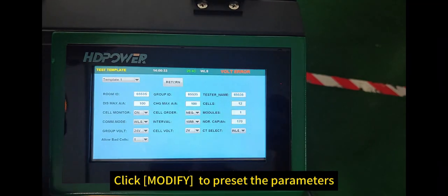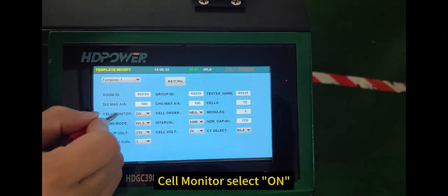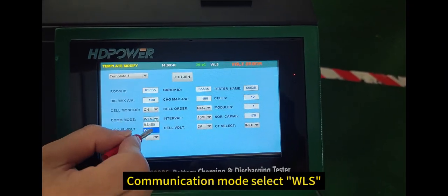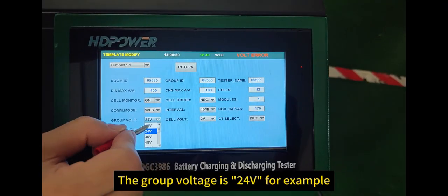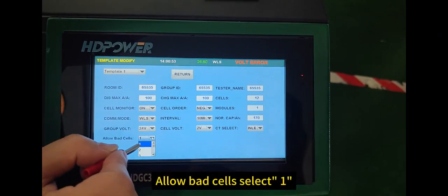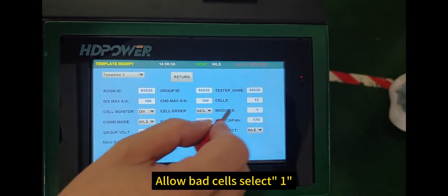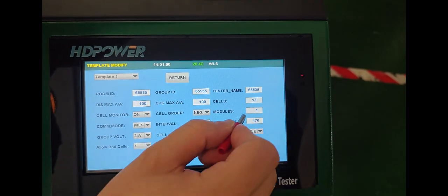Click Modify to preset the parameters. Cell monitor select on. Communication mode select WLS. The group voltage is 24 volts for example. Allow bad cells select 1. The number of battery cells are 12 for example.